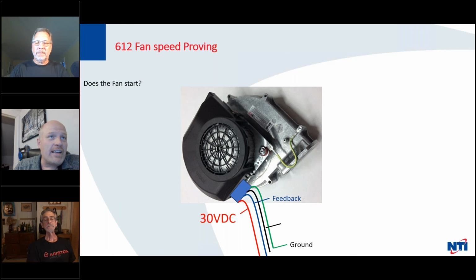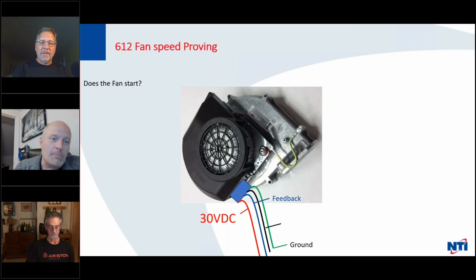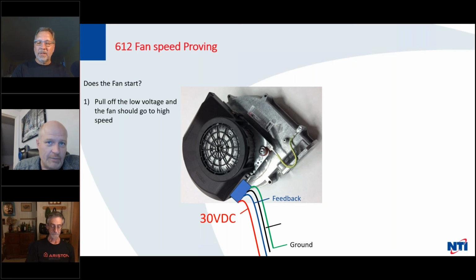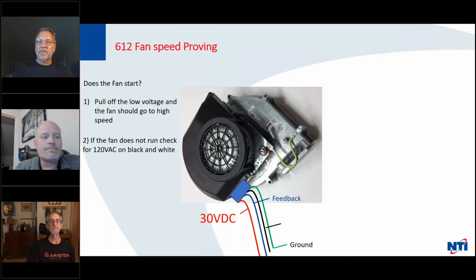612 fan. So this is a fan speed proving error code. So first thing you want to ask yourself is, does the fan start? So if you can hear it starting and running, yeah. If you don't hear it starting and running, find this low voltage connector, remove it. The fan should immediately jump to high speed. If it does not, make sure you've got 120 volt power and you don't have a blown fuse. And I would say 9 times out of 10, what you're going to find is you got a bad fan. You have to replace it. So that one's the easy one.